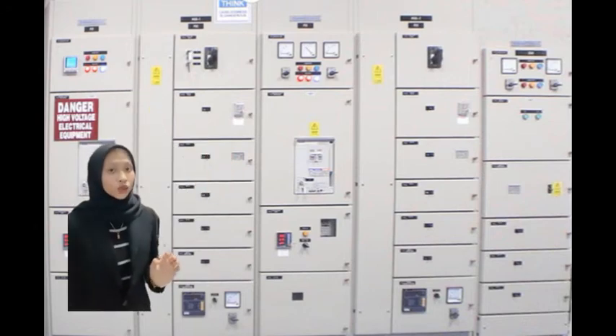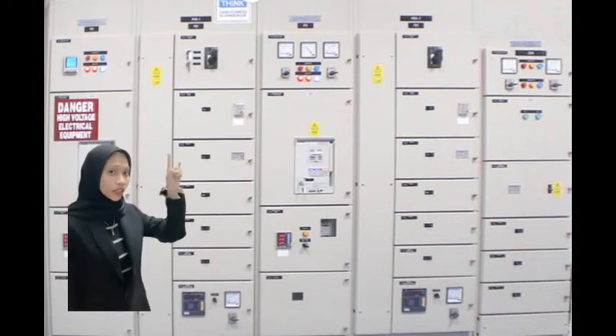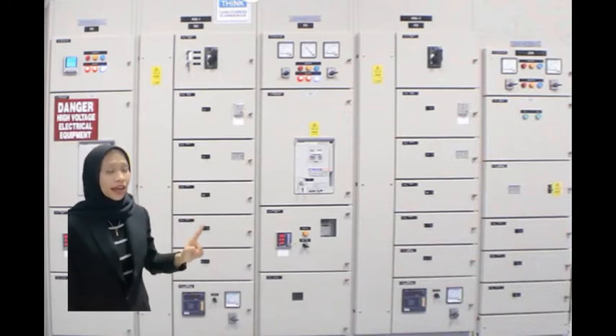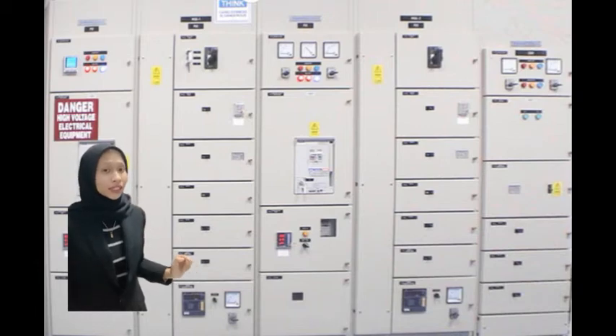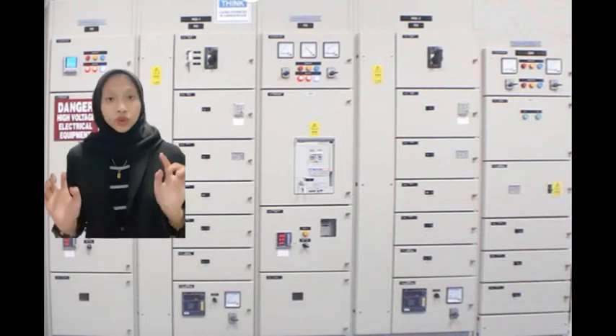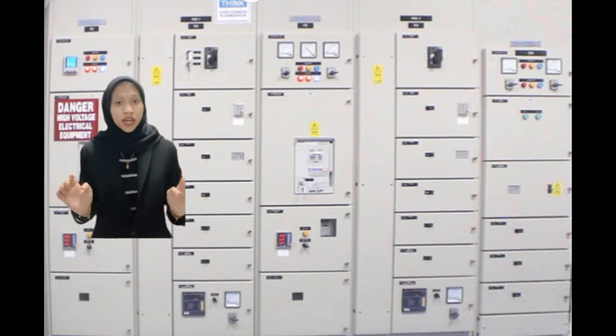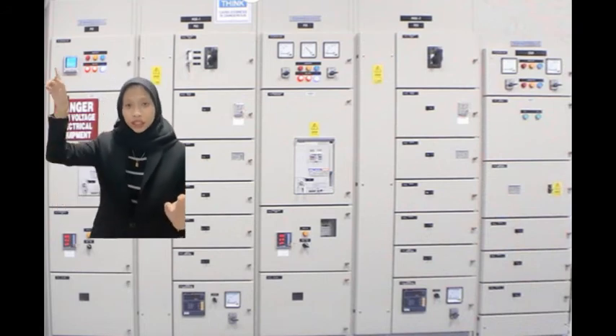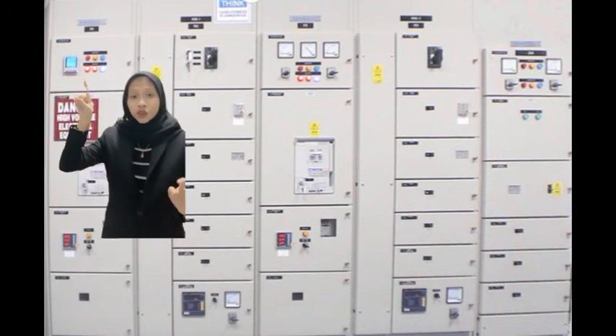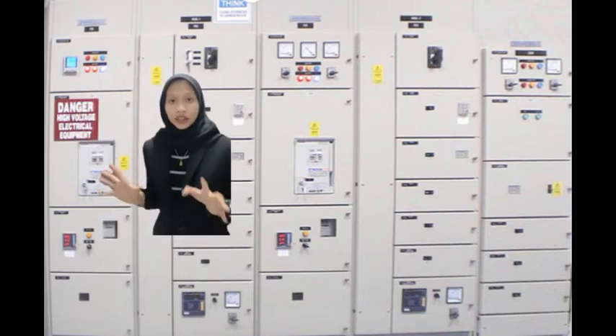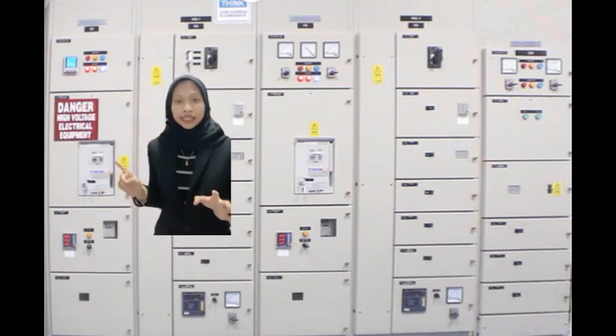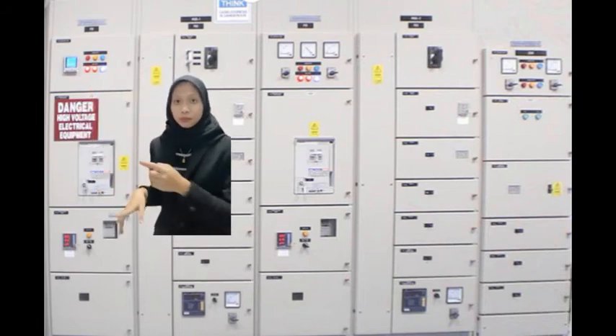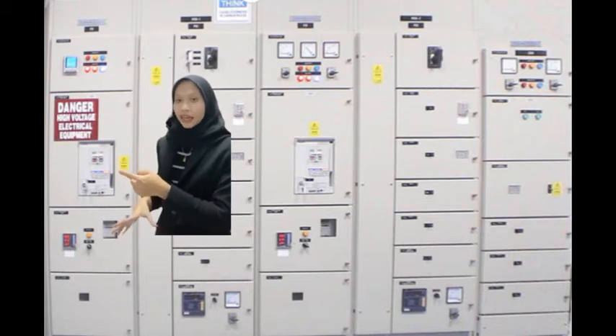And then we must turn off all the loads 1, 2, 3, 4. And lastly, we will turn off the power factor, which is the capacitor factor. To verify, we must check the status at the ammeter. This ammeter should be 0. After that, we can shut down the ACB. We will push the button and then the bus bar is already de-energized.